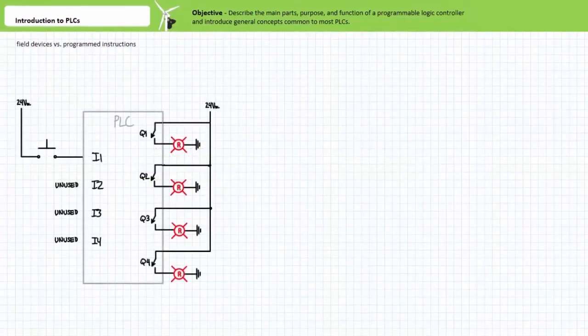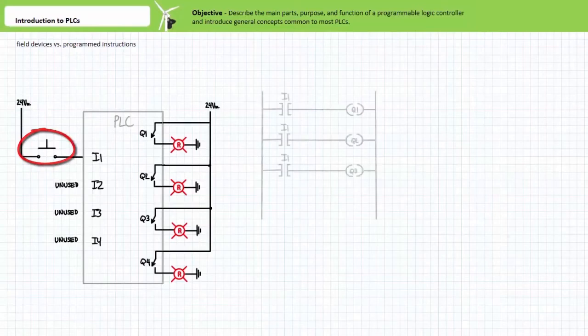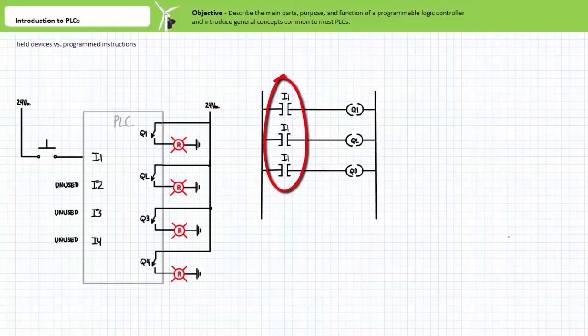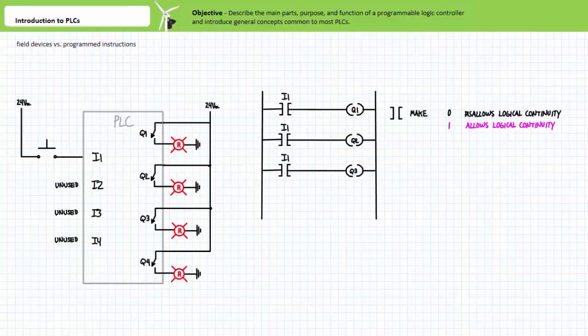A quick example of this important distinction between field devices and programmed instructions could be a single field switch that can be logically instantiated multiple times in a PLC program. Consider a 4-input, 4-output PLC with a normally open field input device on input 1. However, this is logically instantiated three times using a make instruction controlling three separate outputs. The make instruction disallows logical continuity anytime the field input device sends a logical 0 to input 1 and allows logical continuity anytime the field input device sends a logical 1 to input 1.